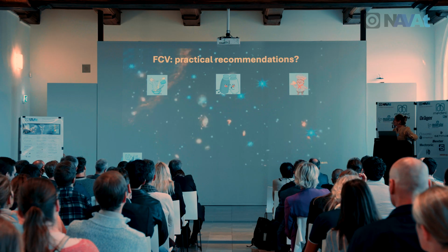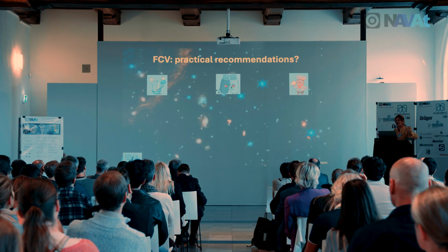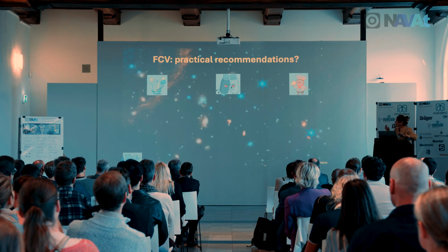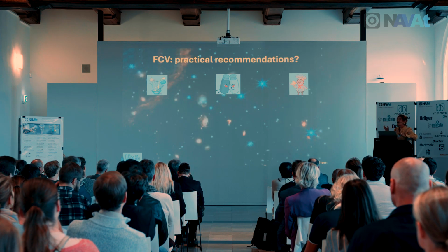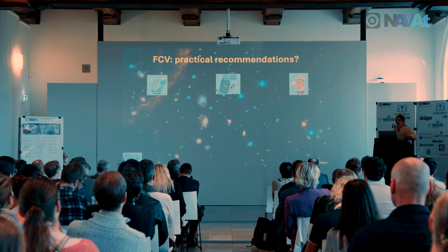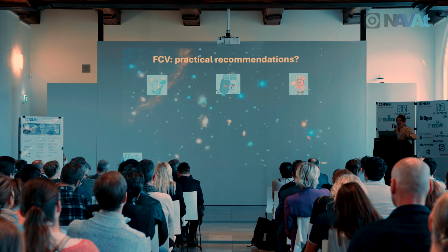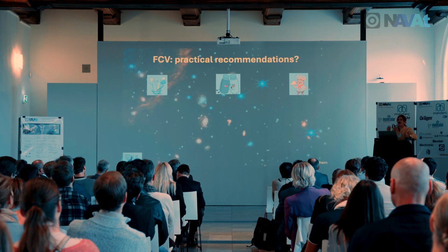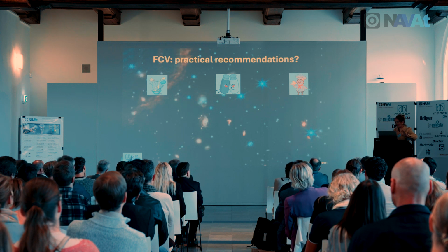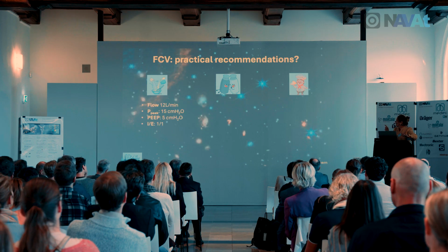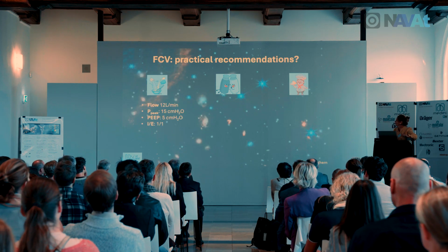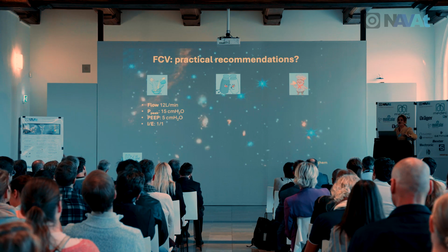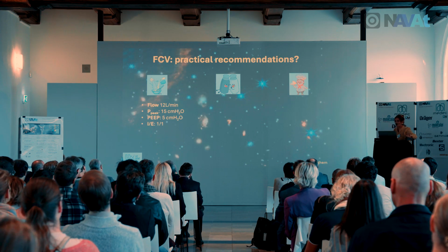Now, how would we start flow-controlled ventilation? What are the ingredients to start a successful flow-controlled ventilation? Here it is important to acknowledge that it is a totally different mindset to use this kind of ventilation technique. Instead of normally setting our tidal volume and our respiratory rate, we do it quite differently. We are setting our flow, our peak, and PEEP. The I:E ratio is ideally 1:1.